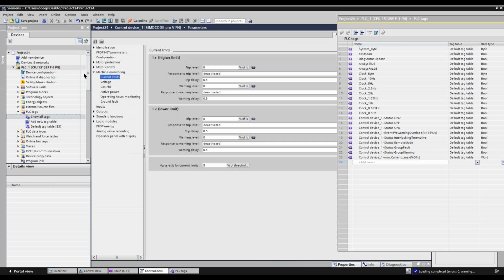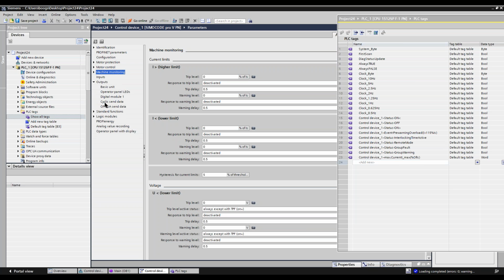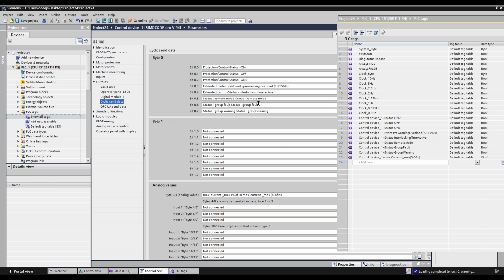Sorry about that. Control device. And I'm going to go to outputs and then to cyclic send. So it automatically sends and creates tags. If you notice, bit 0.0, so bit 0 is forward or reverse. If you come right here, look, there it is, the tag. So what it did is it sends all these tags that were in the template for the reversing starter, and defaulted these tags. And when I said create I/O tags, it went right to the PLC and created those tags.